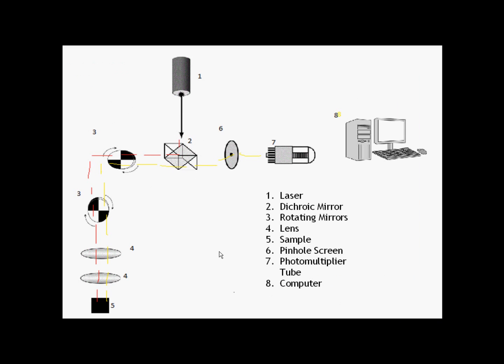This is a schematic created for the Confocal Fluorescence Microscope. It uses a laser to produce the excitation light, which provides high intensities. The laser light, shown as the red line on the screen, reflects off the dichroic mirror, which reflects light shorter than the selected wavelength, then passes through two mirrors that are vertically and horizontally rotating. This allows the laser to scan across the sample, which is why the CFM can also be called a laser scanning microscope.